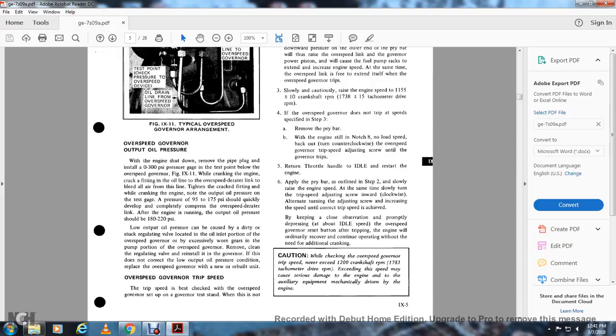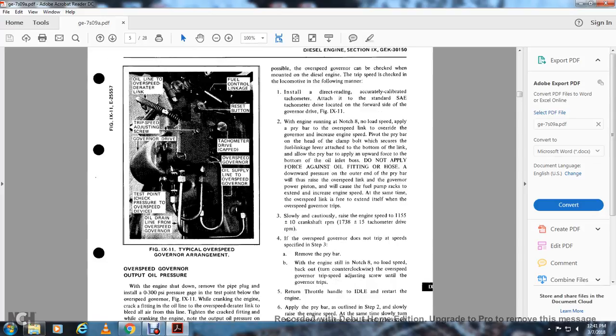Overspeed governor trip speed: The trip speed is best checked with the governor on a test stand. If this is not possible, the overspeed governor can be checked on the diesel engine. The trip speed is checked on the locomotive in the following manner: install a direct-reading, accurately calibrated tachometer at the SAE tachometer drive located on the forward side of the governor drive, figure 9-11.